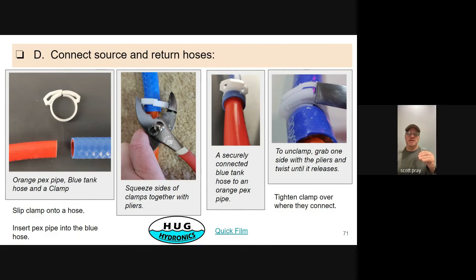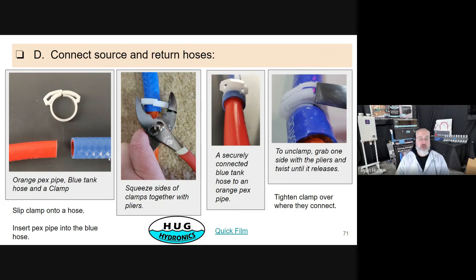Is there a drain at the bottom of the tank for, like, 10 years from now, when maybe the efficiency's gone, maybe it's out of glycol, like an automobile, you run it for 250,000 miles and you've got to replace your radiator fluid? There's no drain on the bottom. What I'd recommend you do is you disconnect one of the hoses from a pump and just run it.